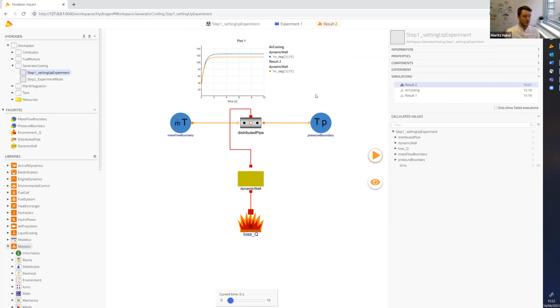What we see here is that the usage of hydrogen has actually reduced the average temperature of the rotor by roughly 10 degrees. That's a very well-known, good effect, due to the fact that the heat capacity of hydrogen gas is very large, about 14 times higher than that of air.